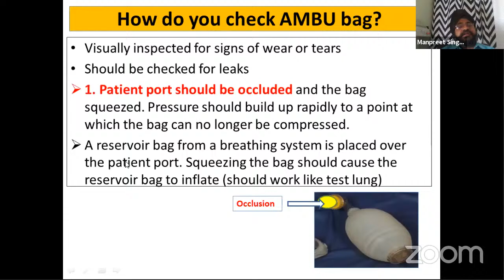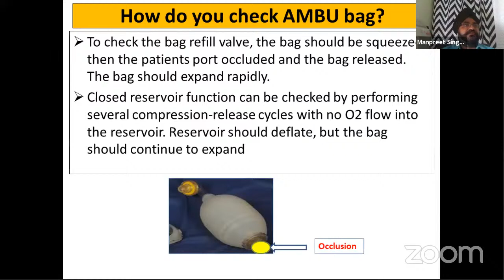You occlude from behind the Ambu both the oxygen port and the bag refill valve area with your hand, and then you squeeze it. If you are not able to squeeze it, this means air cannot be sucked in from there, and therefore there is no leak in the valve. So this is how you should always check an Ambu.